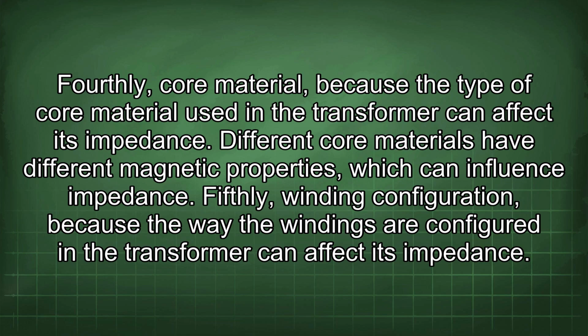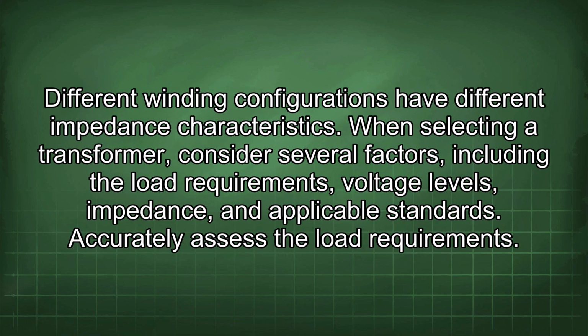Fourthly, core material, because the type of core material used in the transformer can affect its impedance. Different core materials have different magnetic properties, which can influence impedance. Fifthly, winding configuration, because the way the windings are configured in the transformer can affect its impedance. Different winding configurations have different impedance characteristics.